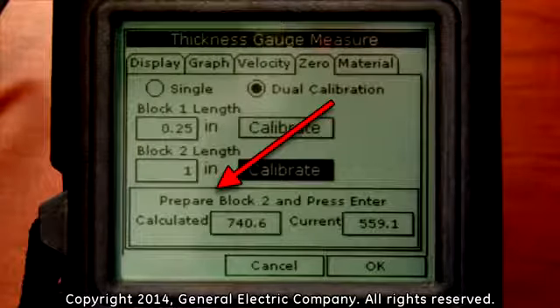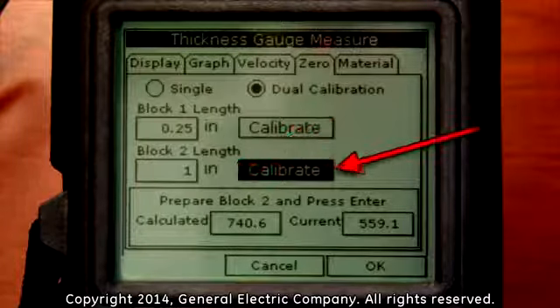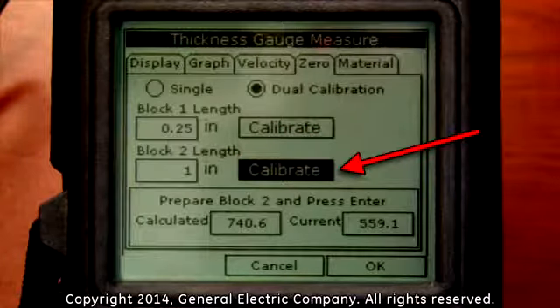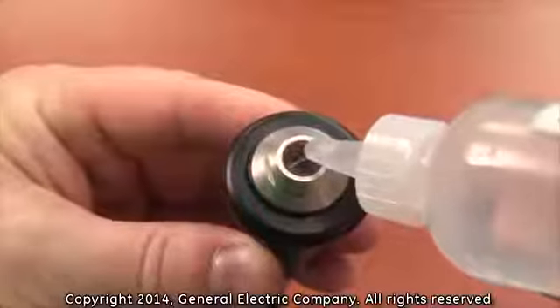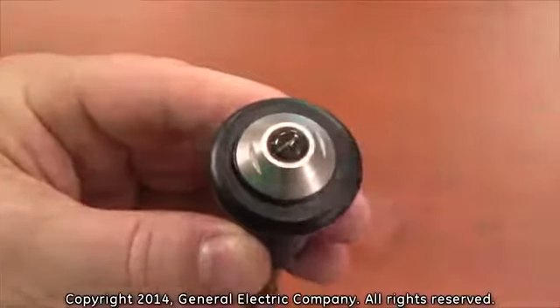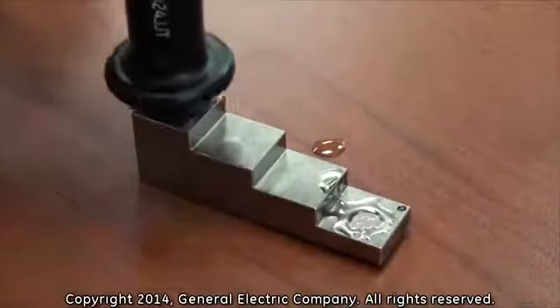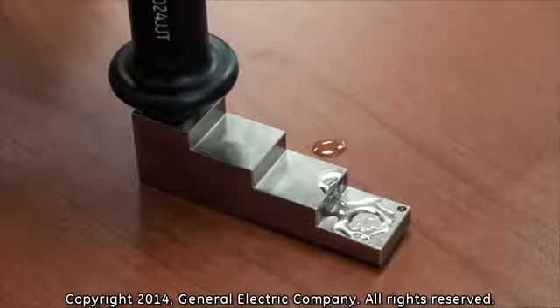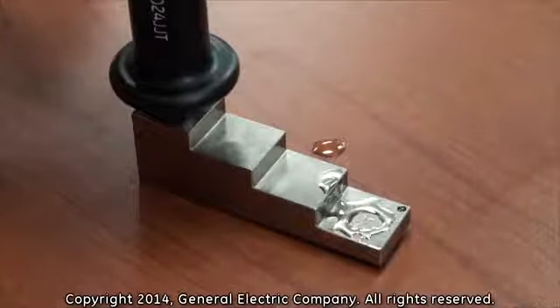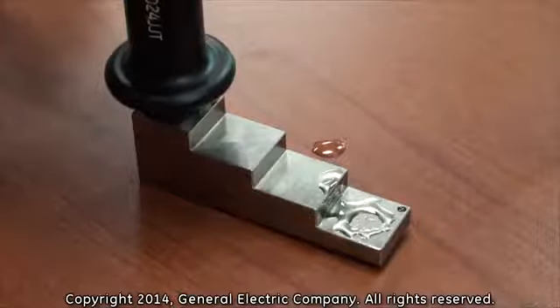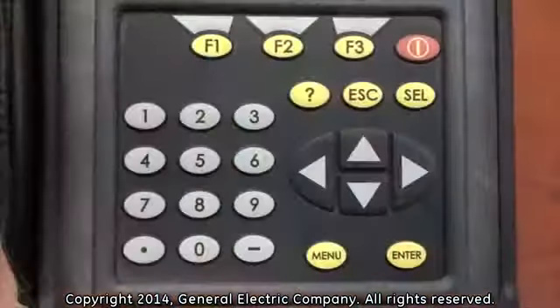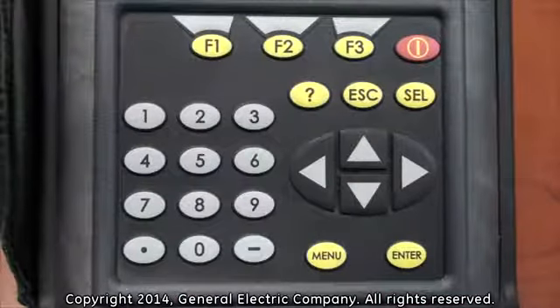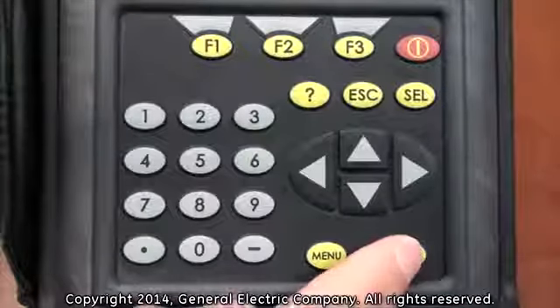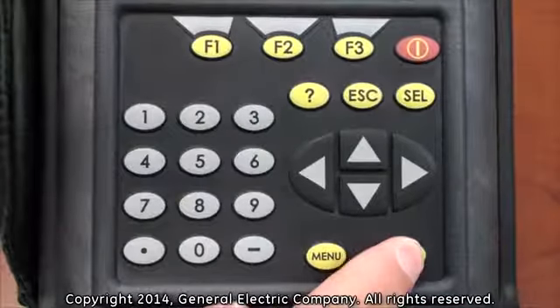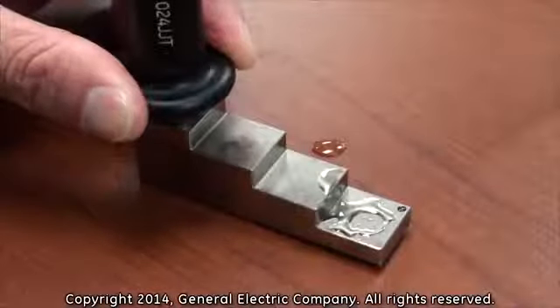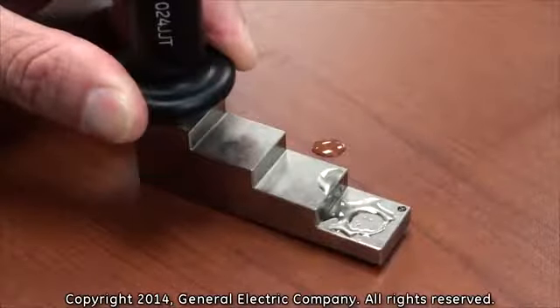You will also see that there is a Calibrate selection field highlighted beside the block 2 length. Apply additional couplant to the face of the thickness gauge transducer and firmly press the transducer to the 1 inch portion of the calibration test block. Remember not to apply too much pressure while pressing the thickness gauge to the test block to ensure a more accurate calibration. With the thickness gauge firmly pressed to the 1 inch portion of the test block, press the Enter button on the keypad when you are ready to calibrate. Hold the thickness gauge steady while the calibration is performed.